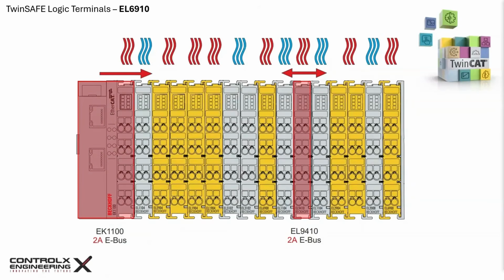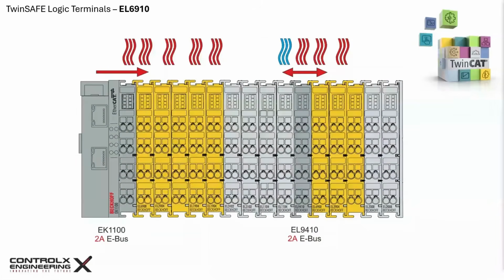It is also a good idea not to place the TwinSAFE terminals next to power supply terminals like the EK1100 and EL9410, as shown. This image shows an example of a thermally bad layout. Here, multiple TwinSAFE terminals are placed together, which may lead to the maximum permissible temperature of the devices being exceeded. The maximum permitted internal temperature is 95 degrees Celsius, above which the TwinSAFE terminals switch to safe state and report an error. The internal temperature can be read from the TwinSAFE component via its CoE. Above this temperature, the TwinSAFE component automatically switches to the safe state called global shutdown and reports an error. Avoid doing this at all costs.